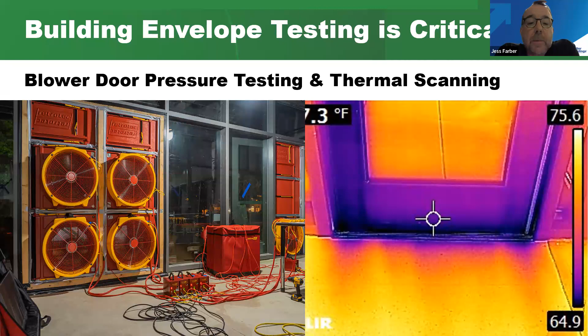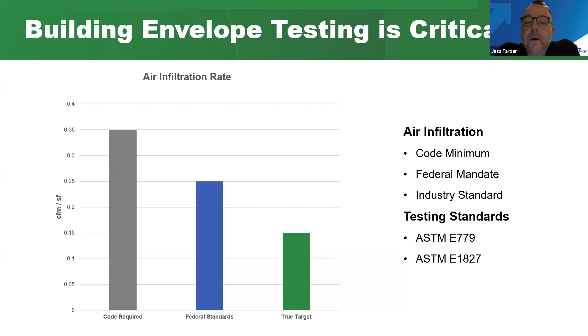There are a lot of standards around building envelope pressure testing. There are code requirements, which are ever changing, and thankfully we see those reducing. There are federal standards too. But if you want a building that performs well, is low energy, and strikes a great balance between building envelope and HVAC tonnage, you want to push even lower. We see 0.15 CFM per square foot of building envelope as a great target that's easily achievable, in both new construction and renovation projects. Make sure you understand your goals and objectives and push the envelope so these heat pump systems work the way you expect.